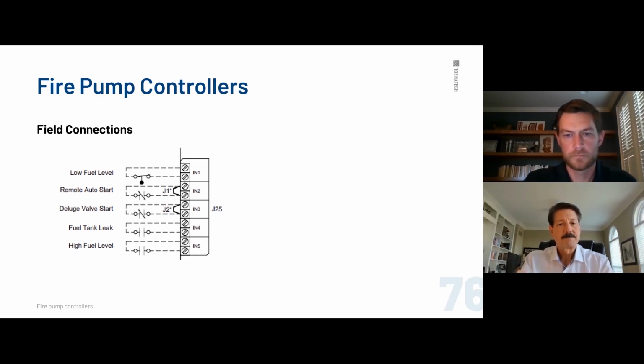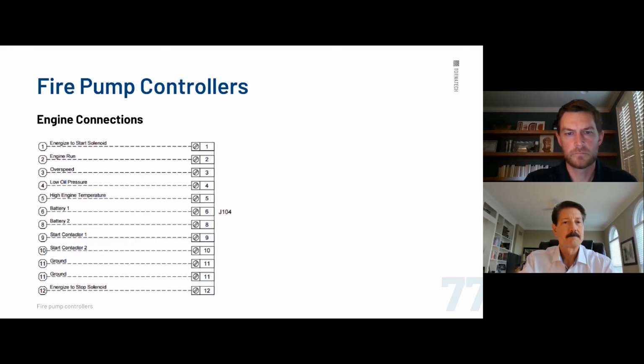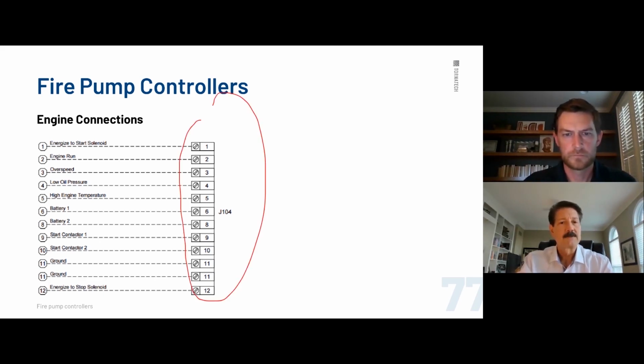Field connections. So, again, I'm just going to cover a few of these here, but fuel level, remote auto start, deluge start, fuel tank leak, high fuel level. Those are all standard. Engine terminals we talk about here. Again, what I'll point out is 1 through 11 used to be what it was probably 10 years ago, but now we go 1 through 12. And 12 is, for a lot of the engines now, you energize to stop.